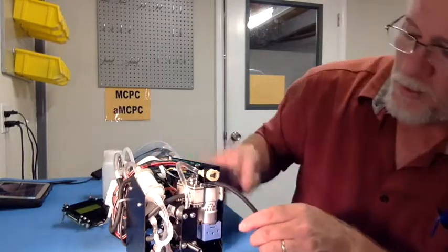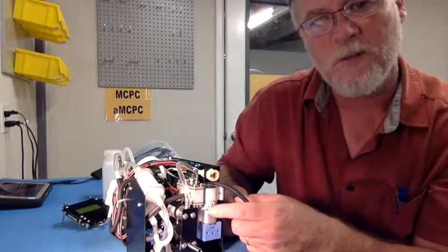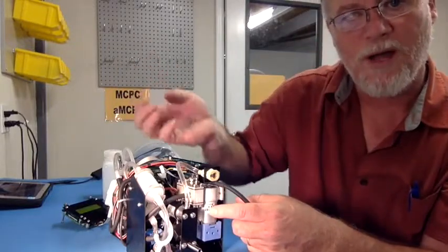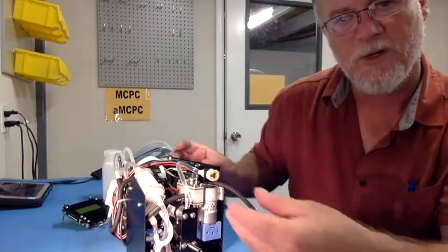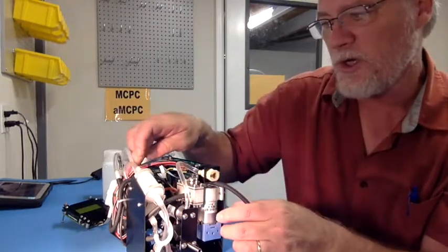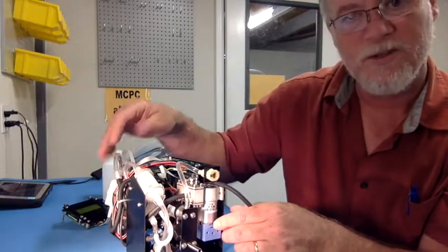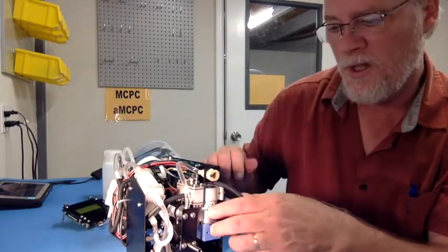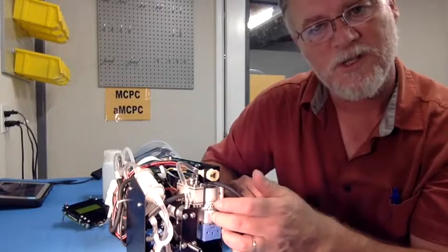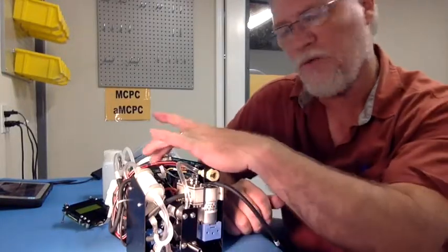All right, continuing around the unit here, you can see this is the exit vacuum pump. This is the pump that's drawing all the flow out of the optics block. So the saturator and the sample flow have combined inside the unit. They're coming out through a critical orifice on the side here. There's some dilution flow that's added to bring down the butanol concentration.